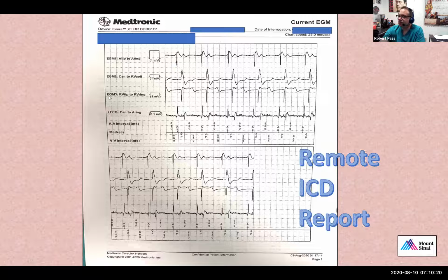Let's go down to the third one here, electrogram 3. This is RV tip to ring. This is what is recorded between the two electrical electrodes at the tip of the lead. And we see here a nice large ventricular electrogram for every QRS. Okay, so you can see here's the A in our atrial and here's the V. And you can see that there is an artifact related to the T wave. So when programming this device, it's important to make sure that the sensitivity is not too high, or else you might double count this artifact here.